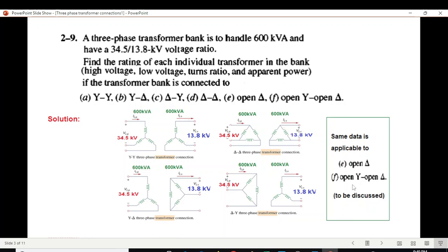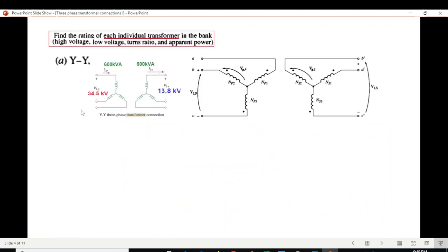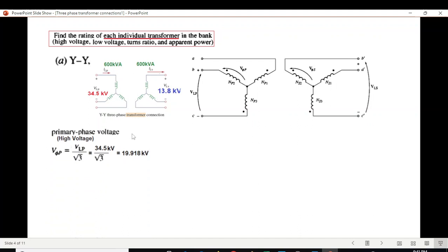Open delta and open-Y open-delta will be solved at the end of this lecture. For the YY connection, we first find the high voltage, which is on the primary side — the primary phase voltage. For a Y connection, the phase voltage equals the line voltage divided by √3, so 34.5 divided by √3 equals 19.918 kV.